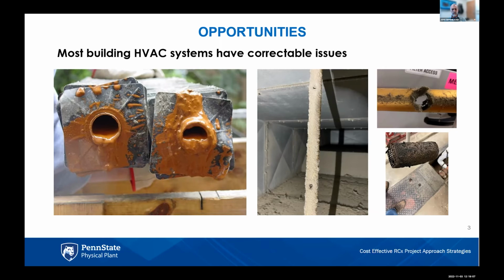Some of these pictures are examples of good intentions that were started for energy savings, but where they overlooked a critical item. The picture on the left is, with BAS systems, you can do a good job with scheduling. This is a dormitory fin tube, and we were turning off the hot water in the summer. But what wasn't happening was that the water was getting circulated. So the chemical treatment agents that the maintenance staff was using weren't getting circulated properly, so it really wasn't being effective at all. We're getting big-time corrosion in certain buildings.